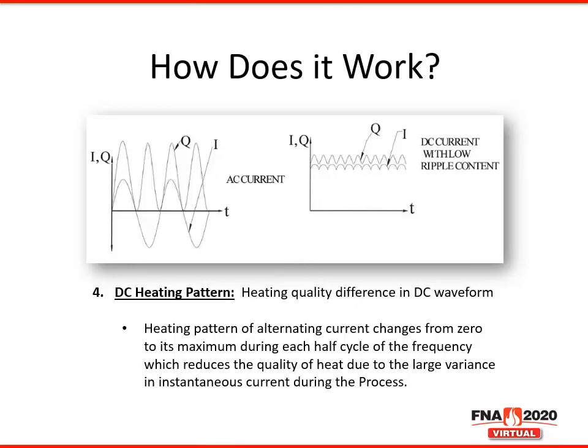The fourth source of efficiency in the IGBT MFDC system is the DC heating pattern. Simply put, a DC heating pattern is better than an AC heating pattern. The graph on the left shows the heating pattern of alternating current. The heating pattern of alternating current changes from 0 to its maximum during each half cycle of the frequency. This reduces the quality of the heat due to the large variance in instantaneous current to the process. The DC waveform, shown on the right, demonstrates a more stable heating pattern and makes heating more efficient.